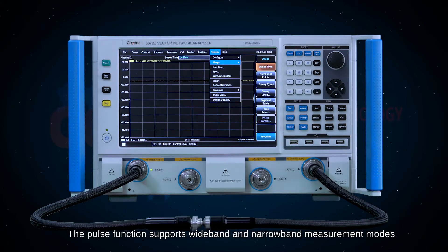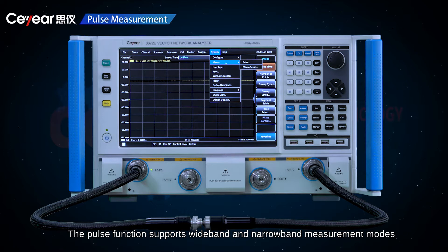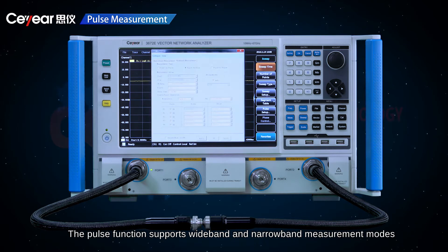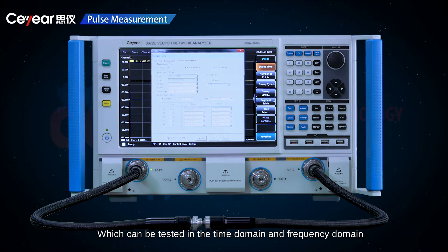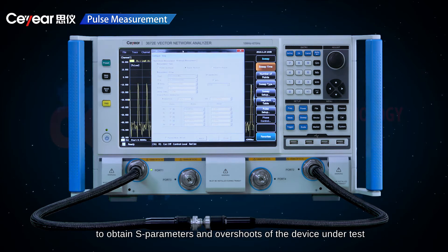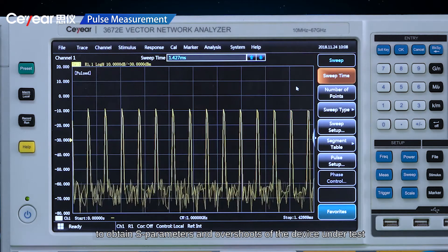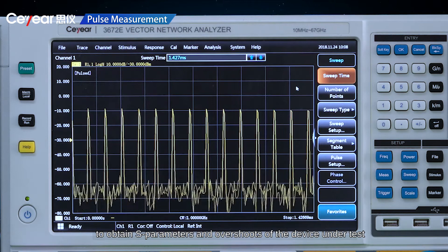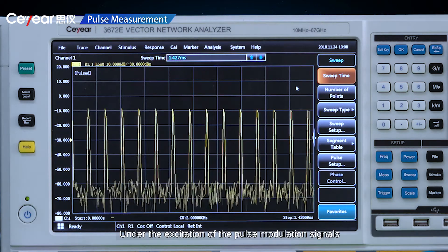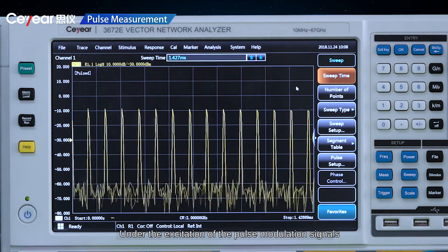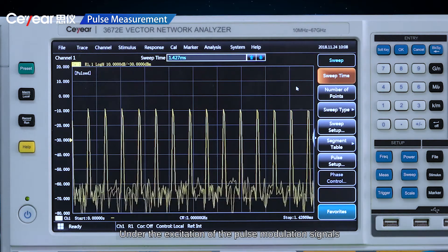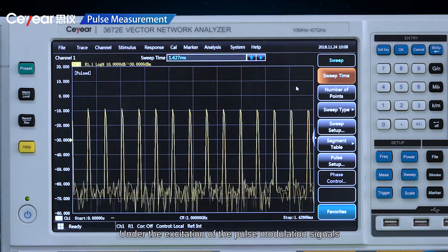The pulse function supports wideband and narrowband measurement modes, which can be tested in the time domain and frequency domain to obtain S-parameters and overshoots of the device under test under the excitation of the pulse modulation signals.